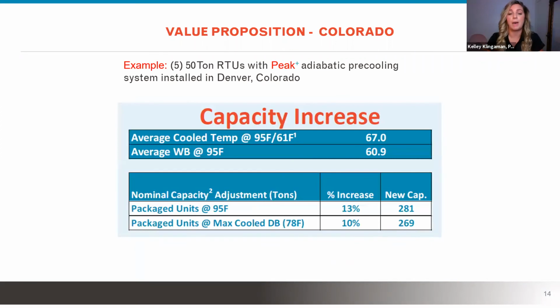To review capacity increase, same situation: if we're talking 5 50-ton units, at the max cooled dry bulb of 78 degrees, we see a 10% increase — from 250 tons as your capacity to 269 tons with our system in place. Definitely something to consider.